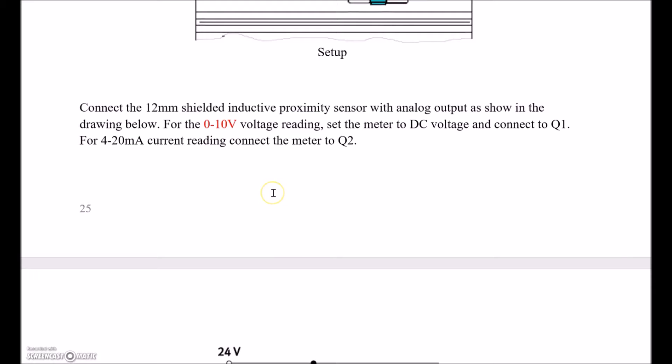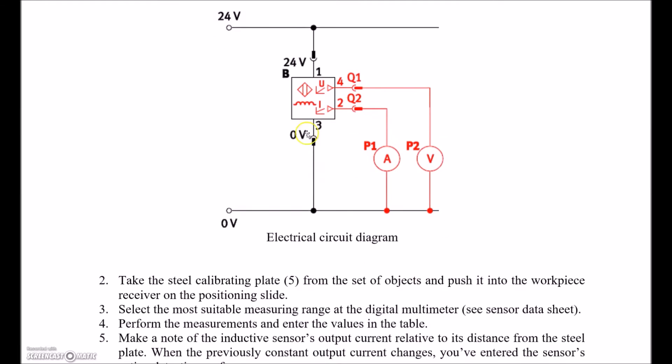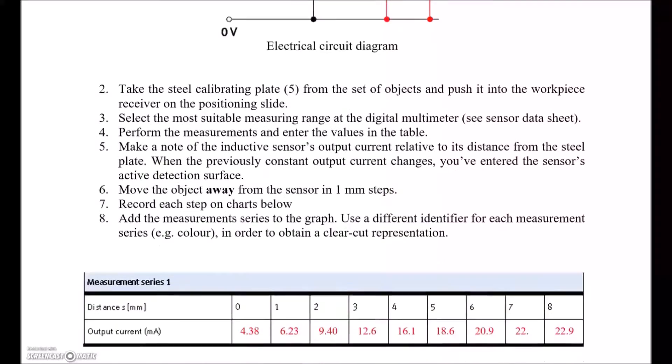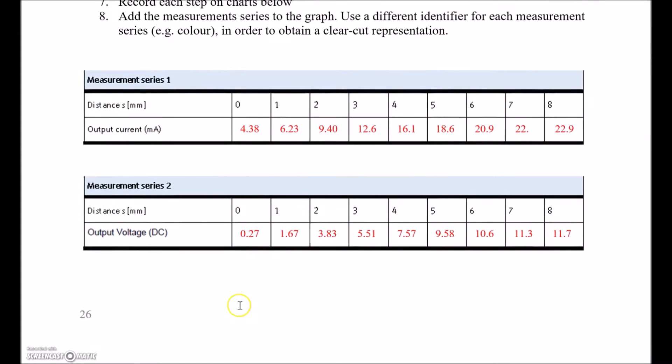And we're going to connect the M12 to give us the 0-10 volt output first. So we're going to connect up to Q1 to our meter. No load needed whatsoever, we're just going to connect up the voltmeter to Q1. So let's first take a look at Q1 going to the voltmeter. And we're looking at a 0-10 volt signal. And the nominal sensing distance of this guy is 6 mils. So we should see 0 to 10 volt DC outputting for a 0 to 6 mils nominal sensing distance.